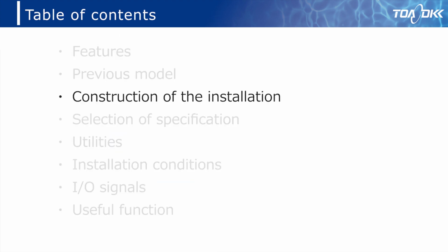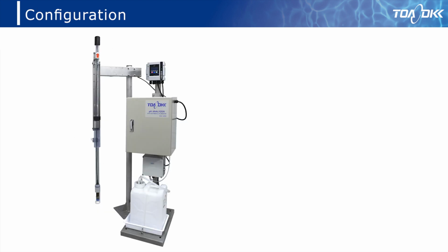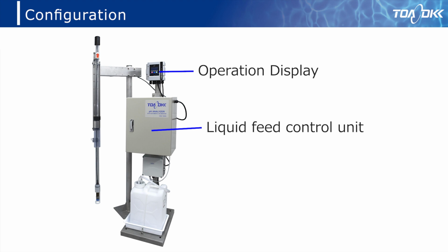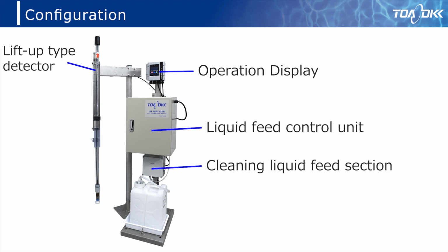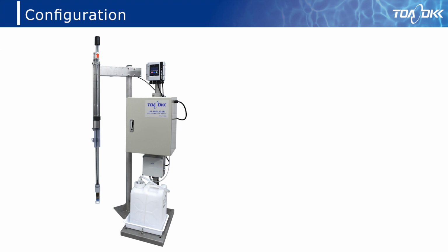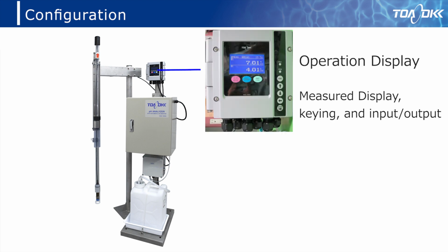This section introduces the configuration of the device. pH meter with automatic calibration function consists of the operating display unit, liquid feed control unit, cleaning liquid feed unit, and lift-up detector. Display of measured value, keying, and input/output are done on the operating display unit. The image shows display of 2-channel measurement.